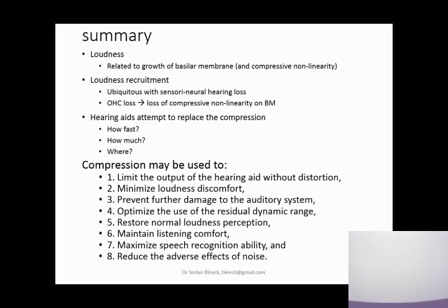That's why we need to do something to increase speech intelligibility specifically, and it has been shown that wideband dynamic compression, where we split it into bands and, individually on the basis of the hearing thresholds in each band, amplify and set the compression ratios correctly, will maximize the speech intelligibility in noise.